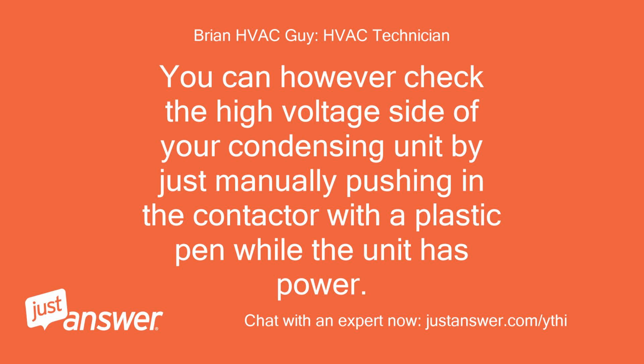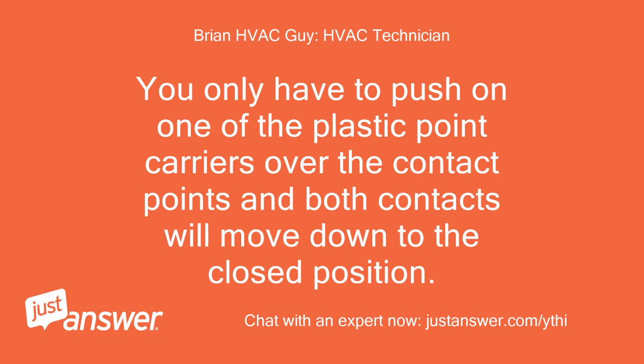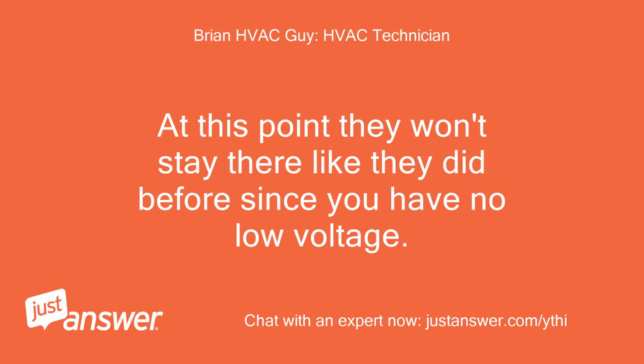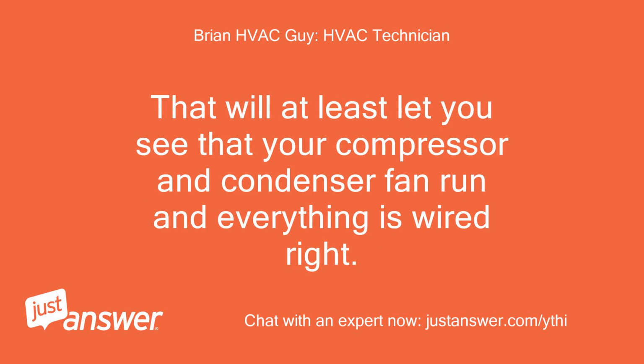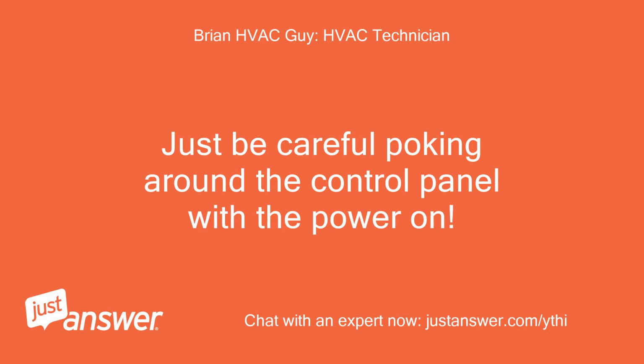You can, however, check the high voltage side of your condensing unit by just manually pushing in the contactor with a plastic pen while the unit has power. You only have to push on one of the plastic point carriers over the contact points and both contacts will move down to the closed position. At this point they won't stay there like they did before since you have no low voltage. That will at least let you see that your compressor and condenser fan run and everything is wired right. Just be careful poking around the control panel with the power on.